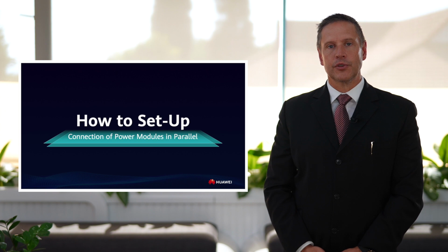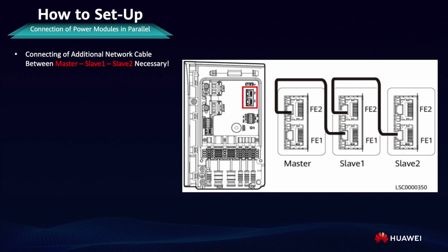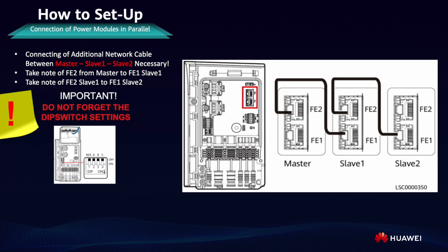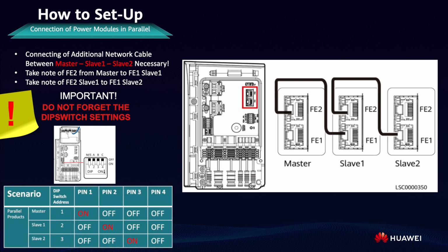Connection of parallel systems on FE port. Connection of additional network cables between master, slave 1 and slave 2 is necessary. Take note of FE2 from master to FE1 slave 1, and FE2 slave 1 to FE1 slave 2. Please pay attention to the dip switch settings, as the unit will not be able to communicate correctly if it's not done properly. The master must be set with pin 1 on and the remaining pins of the dip switch off. Slave 1, if you've got one parallel connected system, will be pin 2 on, the rest of the pins off. In slave 2 configuration, for 3 parallel connected units, pin 3 will be on and the rest of the dip switches will be off.